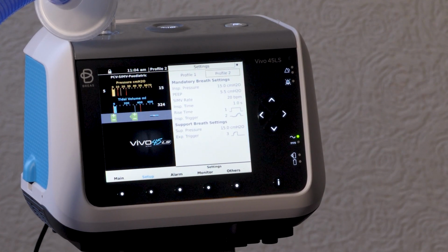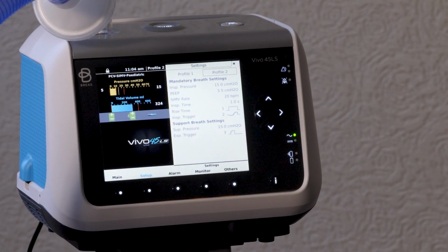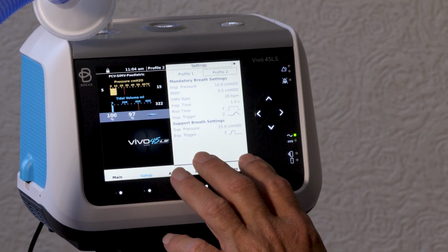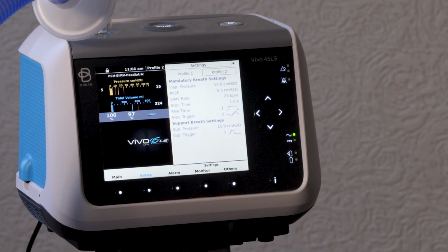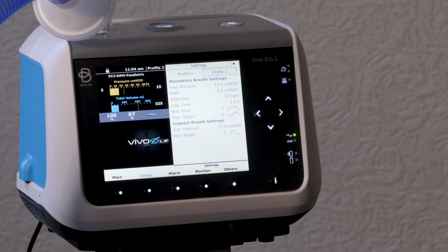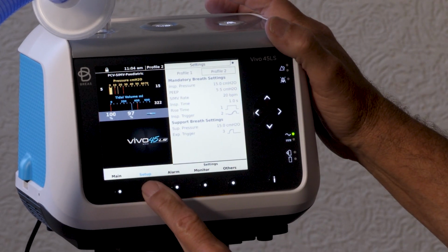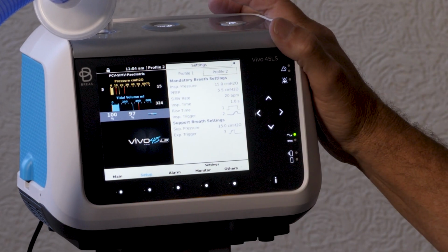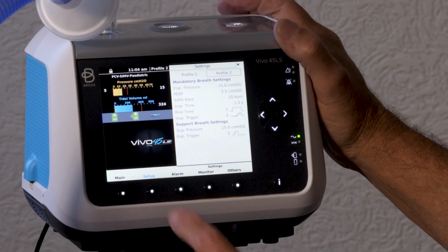So it's important to actually know what your settings should be. If you're just recently being discharged from the hospital, what I try to recommend to caregivers, parents, if it's a kid or whoever, is to take a picture of your settings and know what your settings are. We don't want somebody coming in and changing your settings without you being aware. So if you ever want to check on your settings, you simply hit the setup button and you can verify your settings. Now let's go over to the alarm button.